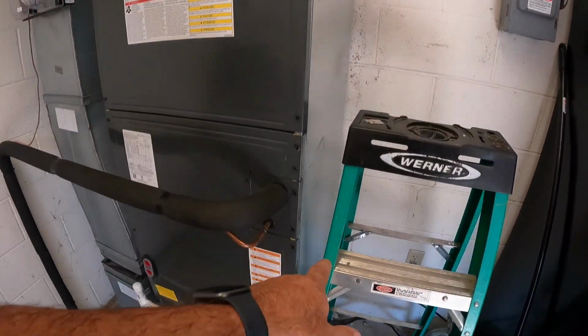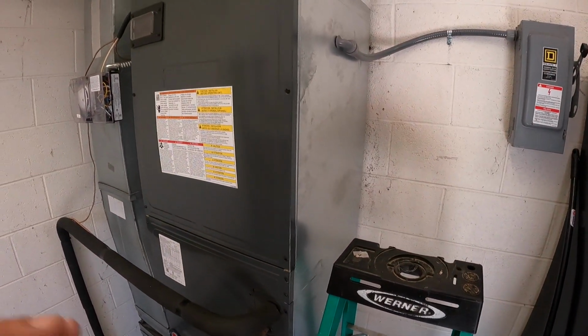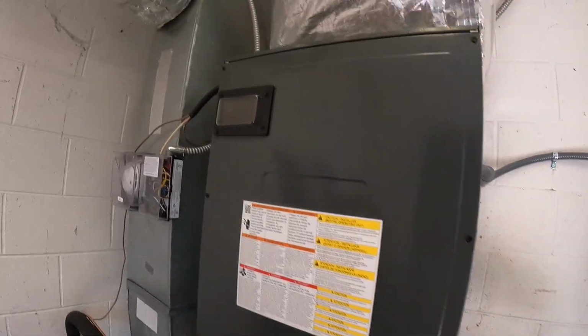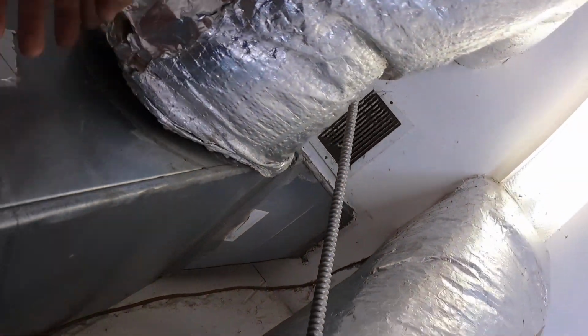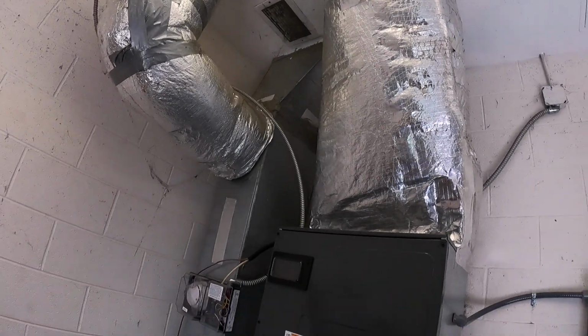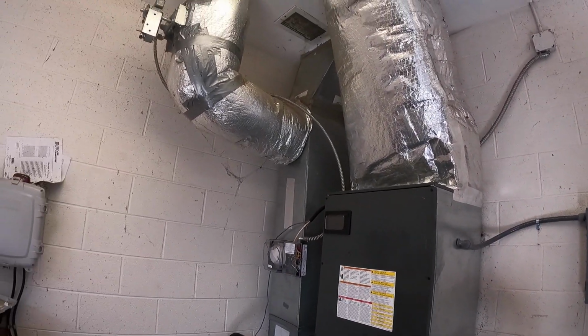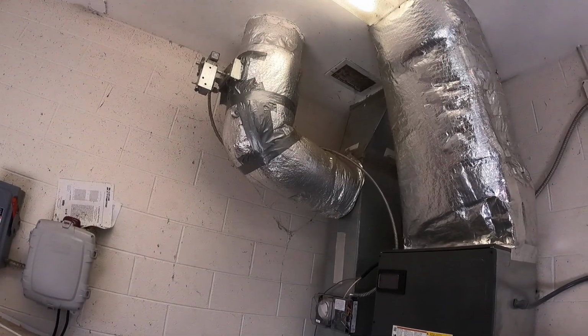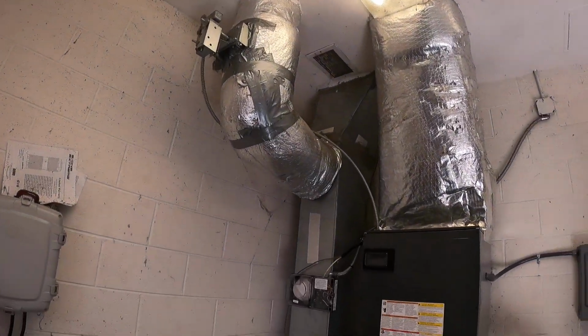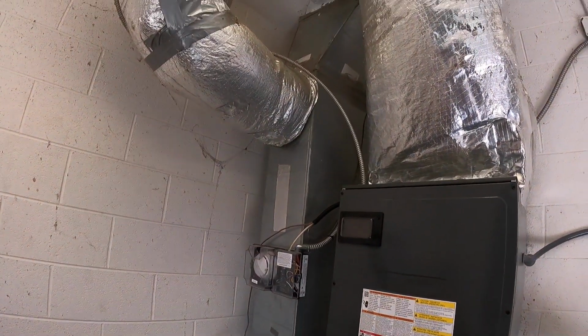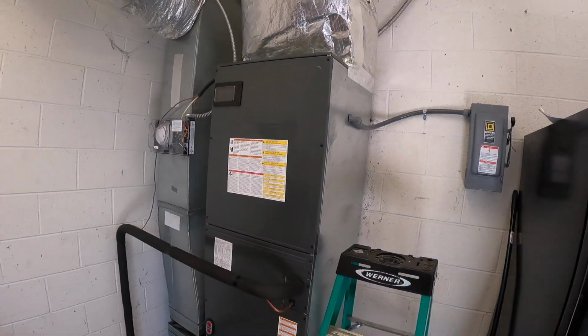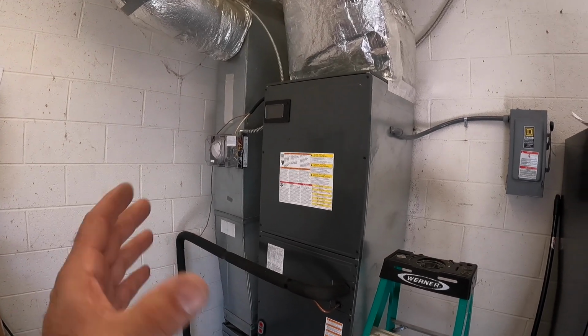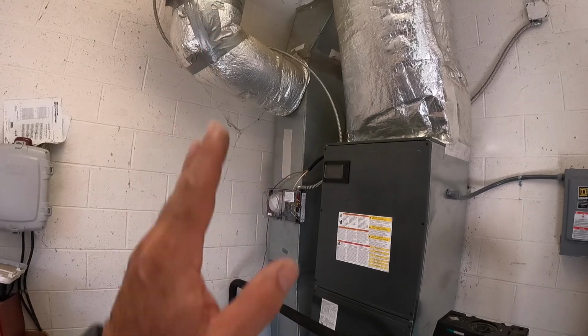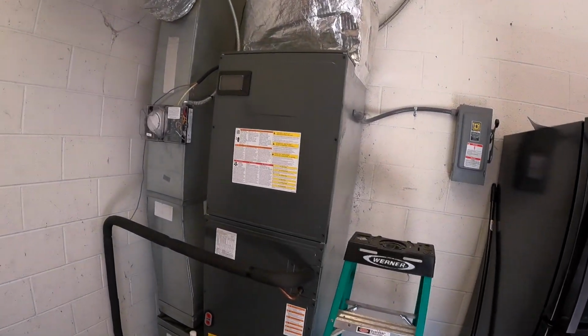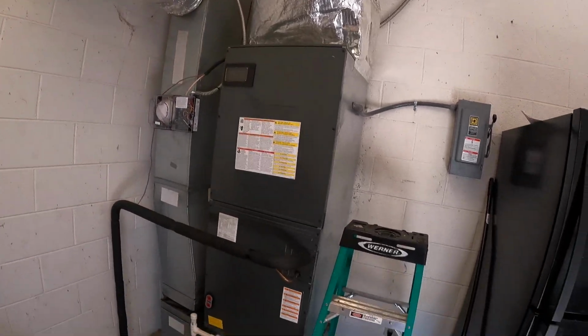One thing I forgot to mention was when we were doing the static, you might have noticed even though I slowed the fan down, the static increased. The reason is we shut down a damper right here on this fresh air. The maintenance guys came by in the middle of me doing the speed tap test, and they wanted to limit the amount of air because that damper's cranking wide open up there. I said, well, maybe they put a damper right here, and sure enough there was. So we choked down on it while watching the static pressure, and you could tell how much difference it was making. So we're putting a little less outdoor air and a little more indoor air now, so the static went up because it's probably a longer distance.